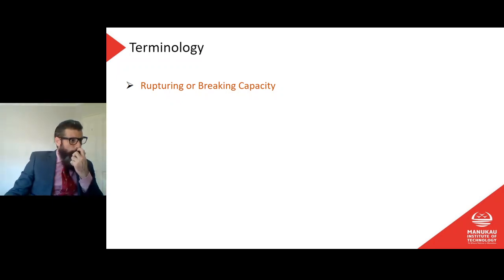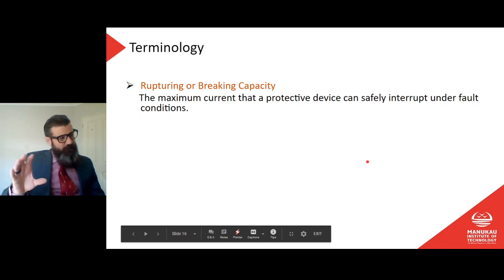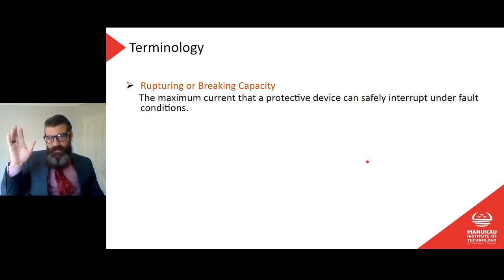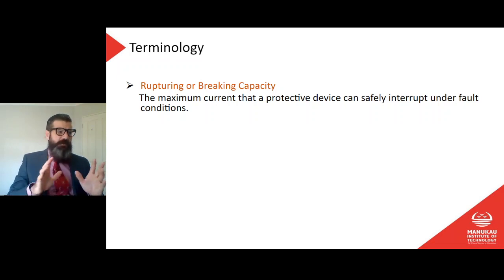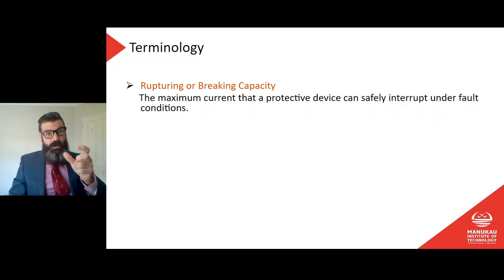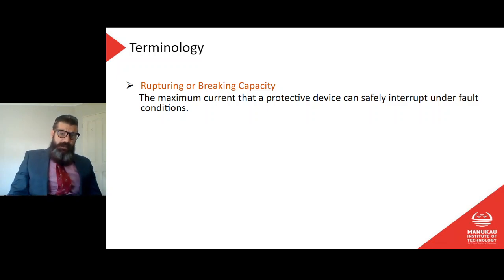What's our next thing? Rupturing or breaking capacity. Cool. This is a good one. I think we've talked about this before, and for some reason it seemed to be something that was kind of hard for people to grasp, but to me this is very simple. It's the maximum current that a protective device can safely interrupt under fault conditions. So this is not about the rating of the circuit breaker. It's not about if you have a circuit breaker that's 20 amps, that's nothing to do with the rupturing or breaking capacity. This is the maximum amount of current that we can push through that circuit breaker and it will still trip.